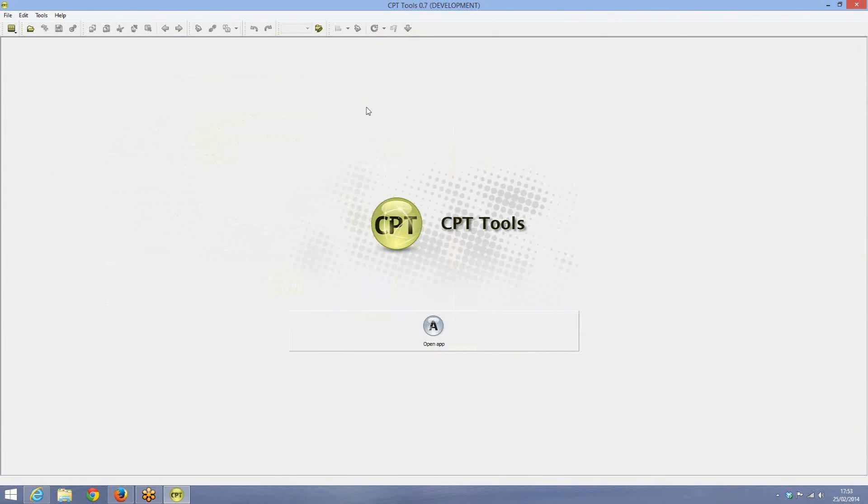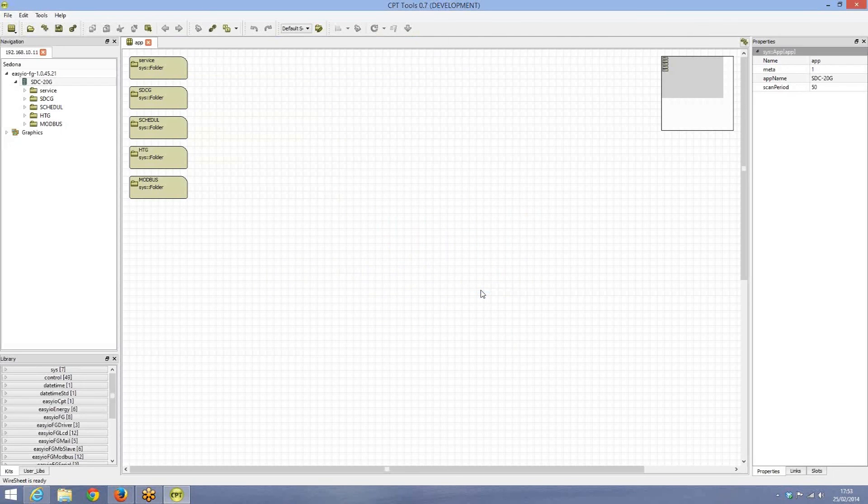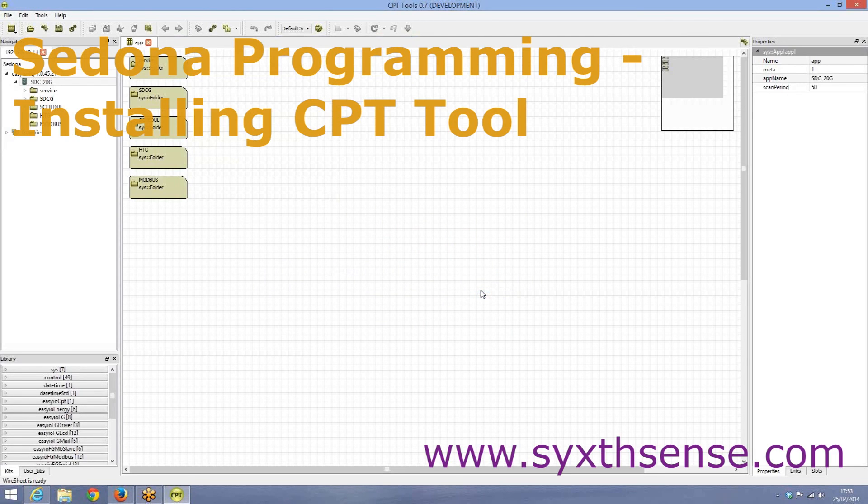When you launch the CPT tool first time, you can see this button here on the bottom which says open app and this is the button to connect to the controller. So if I click that, I basically need to give the IP address of the controller, 192.168.1.10 and a username admin and a password field. We just leave it empty, press OK and this now logs into the controller, in this case SDC-200 controller.